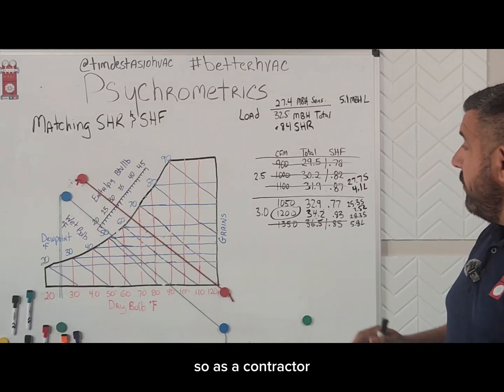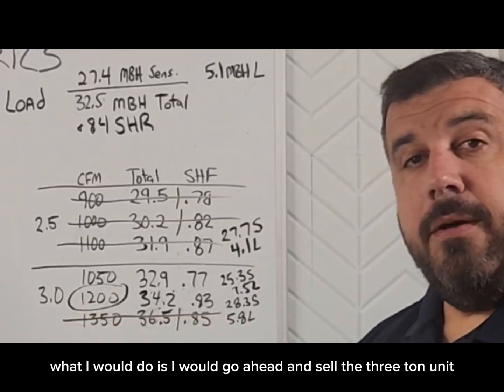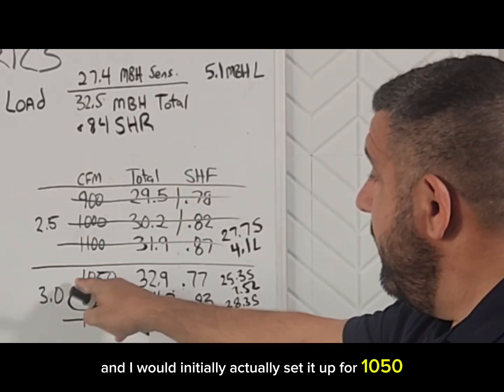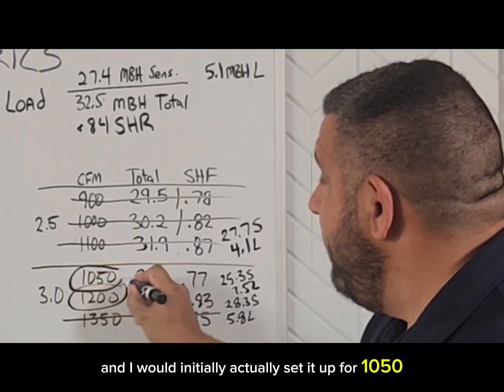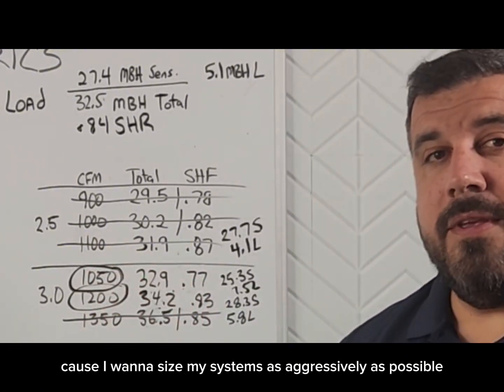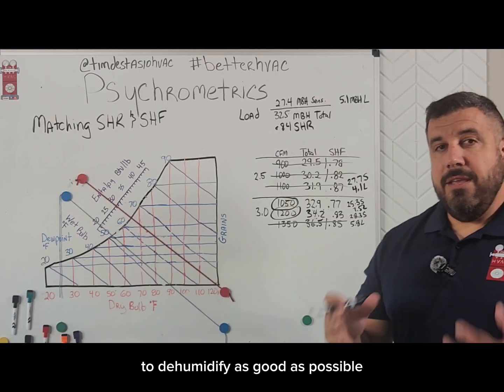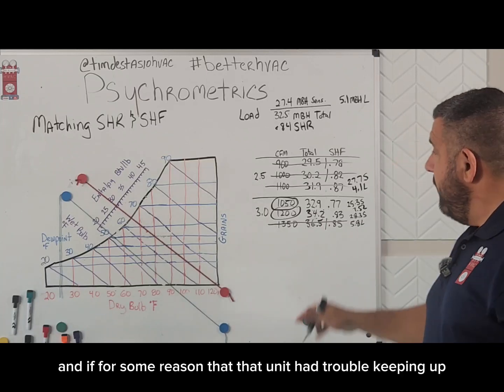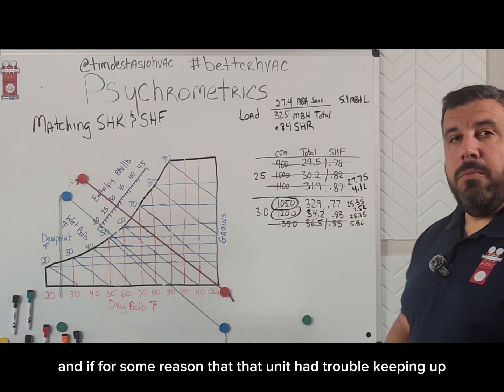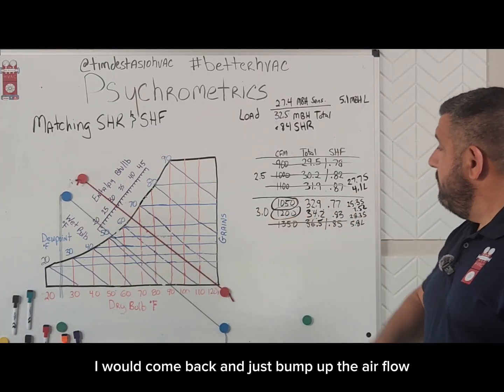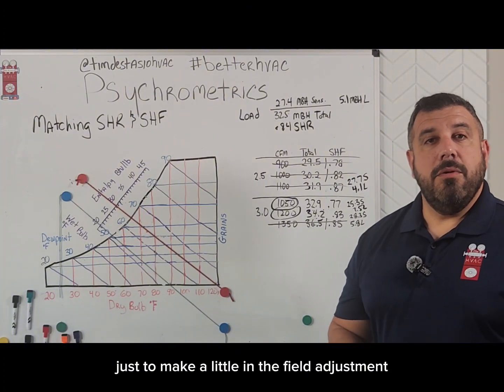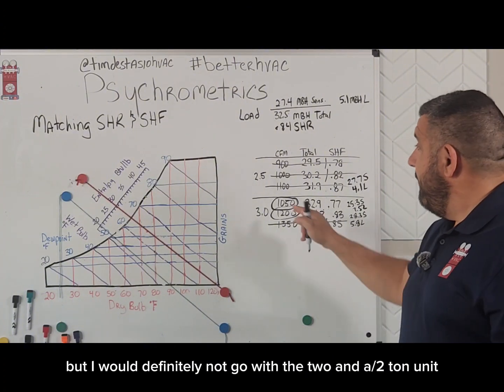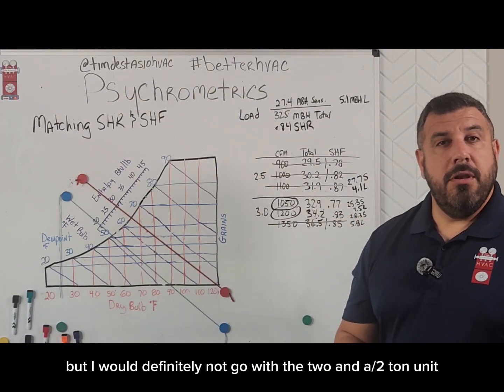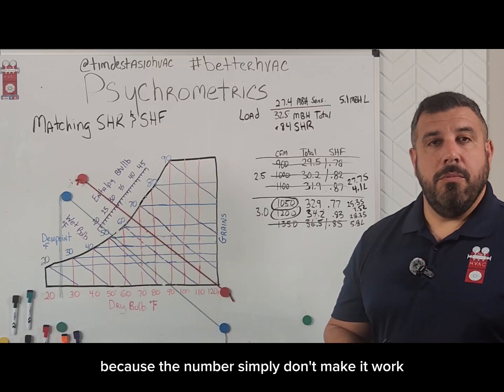So as a contractor, what I would do is go ahead and sell the 3-ton unit, and I would initially set it up for 1050 because I want to size my systems as aggressively as possible to dehumidify as well as possible. And if for some reason that unit had trouble keeping up, I would come back and bump up the airflow as a little field adjustment. But I would definitely not go with a 2.5-ton unit because the numbers simply don't make it work.